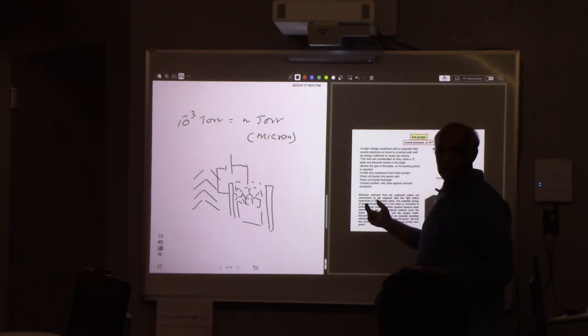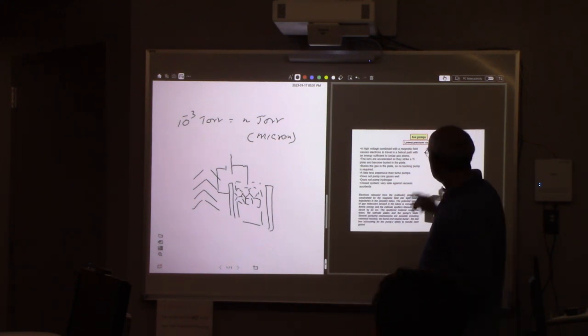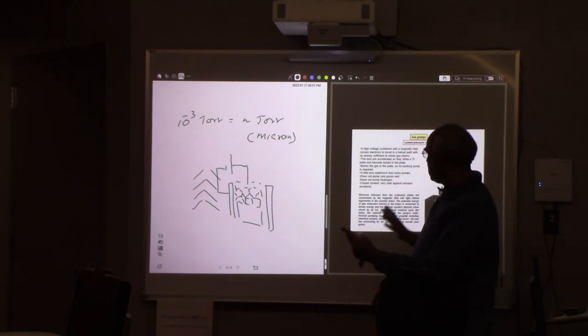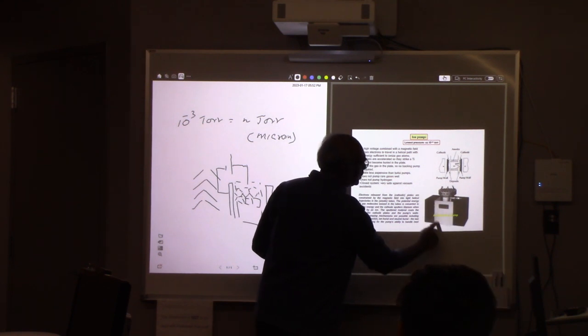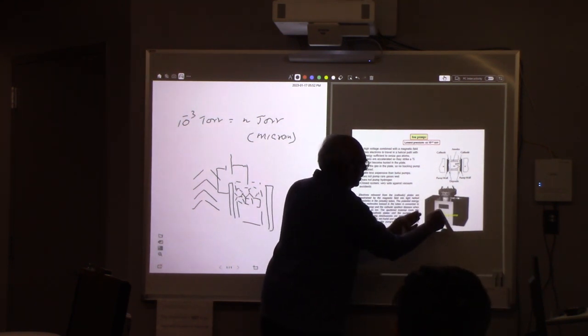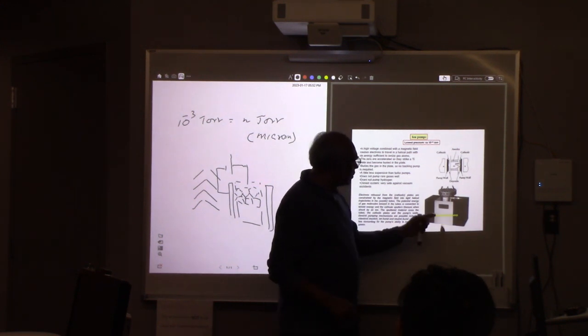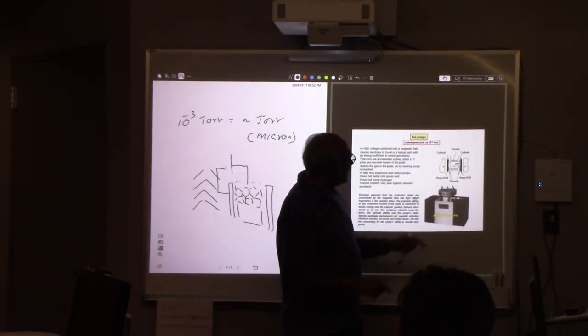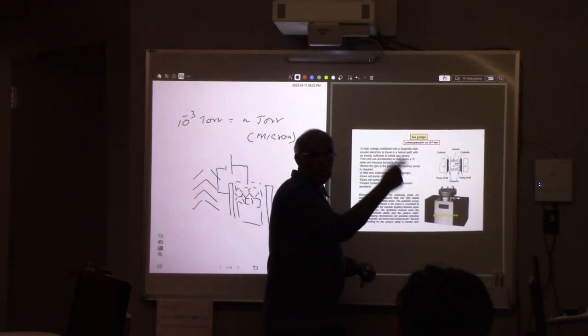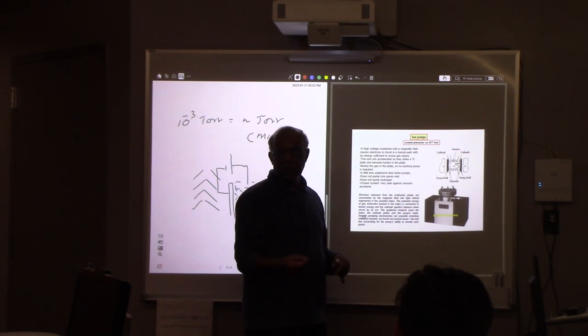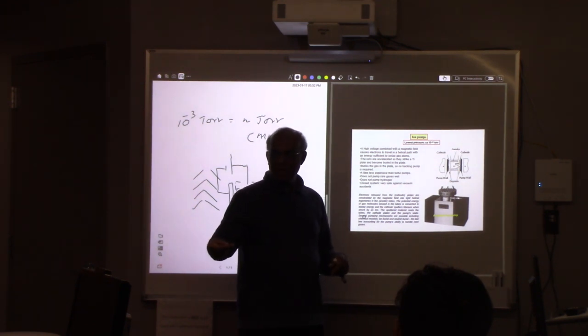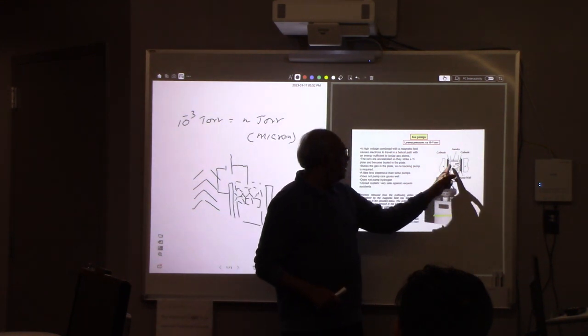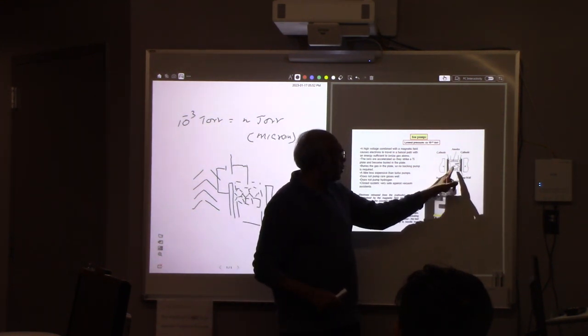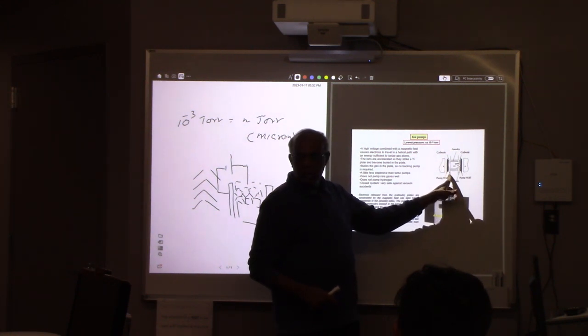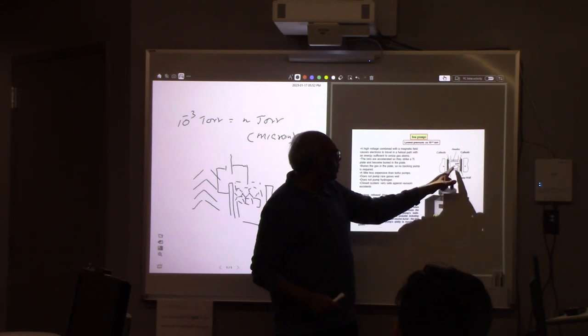Now if I apply a very high voltage, it ionizes the gas molecules, right? It's basically high-voltage breakdown ionization. Then also it's between two magnets. So in this ion pump, these two are magnets. This is the ion pump that has the two cathodes and the anode, and this is the magnetic field. When you apply this high voltage between cathode and anode, that will ionize the gas molecules. Then you have electrons and ions, right? The positive ions will come to the cathode, and the electrons will go to the anode.